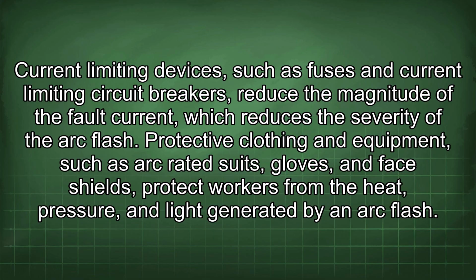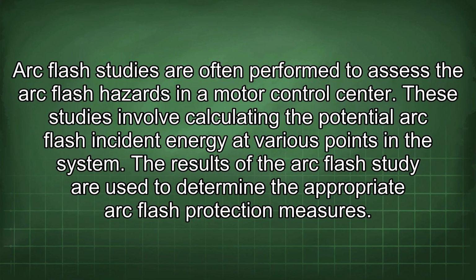Protective clothing and equipment, such as arc-rated suits, gloves, and face shields, protect workers from the heat, pressure, and light generated by an arc flash. Arc flash studies are often performed to assess the arc flash hazards in a motor control center. These studies involve calculating the potential arc flash incident energy at various points in the system. The results of the arc flash study are used to determine the appropriate arc flash protection measures.